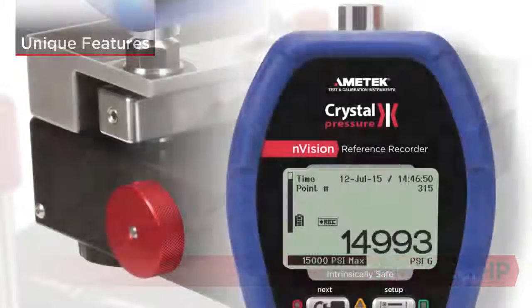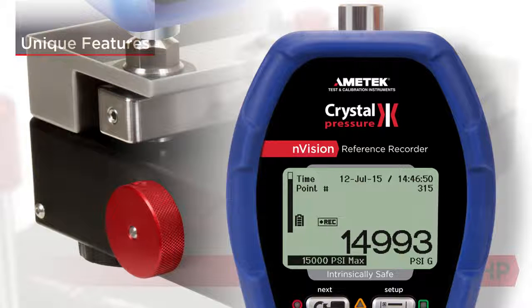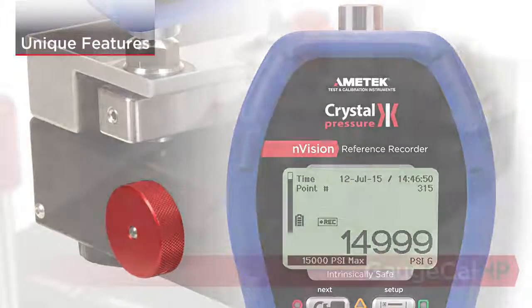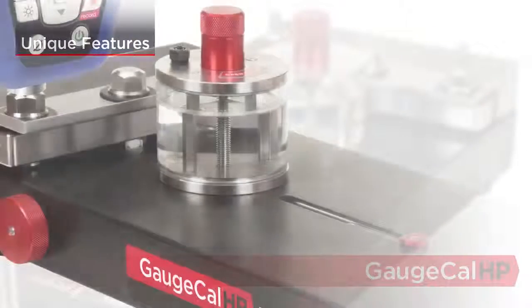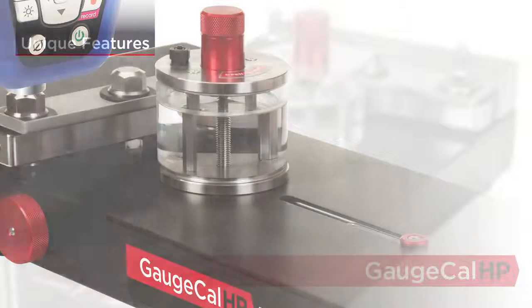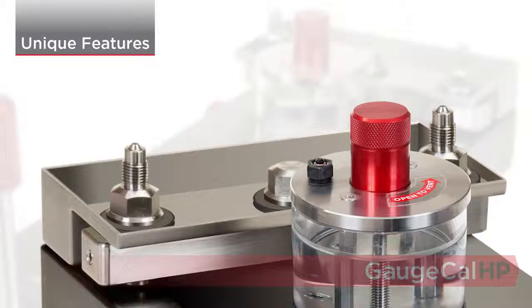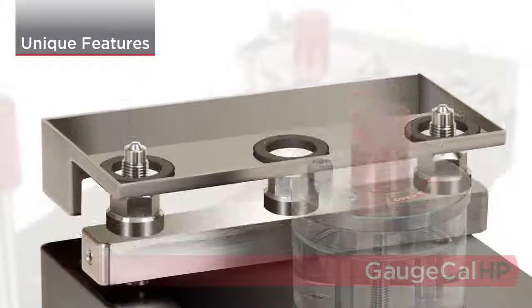Many comparators include fine adjustment knobs, but some can be very difficult to use at elevated pressures. The GaugeCalHP Fine Adjust is easy to use all the way up to the maximum pressure of 15,000 psi. The reservoir is clear, allowing you to ensure the cleanliness and level of the fluid. Each GaugeCalHP includes two pressure ports with our patented finger-tight, leak-free CPF pressure fittings. Under the connection fittings is a removable drip tray that catches fluid expelled while bleeding the system.